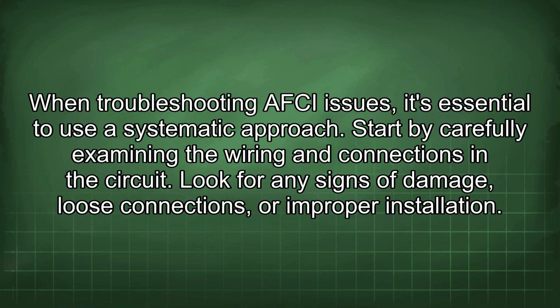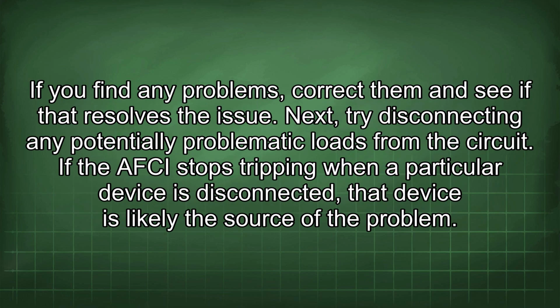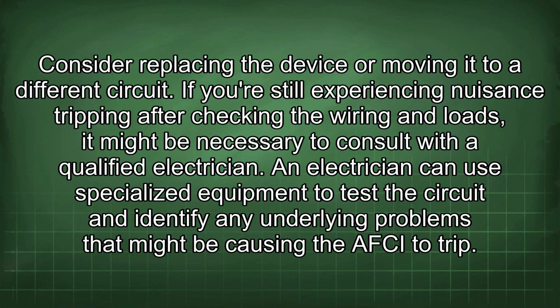When troubleshooting AFCI issues, it's essential to use a systematic approach. Start by carefully examining the wiring and connections in the circuit. Look for any signs of damage, loose connections, or improper installation. If you find any problems, correct them and see if that resolves the issue. Next, try disconnecting any potentially problematic loads from the circuit. If the AFCI stops tripping when a particular device is disconnected, that device is likely the source of the problem. Consider replacing the device or moving it to a different circuit.